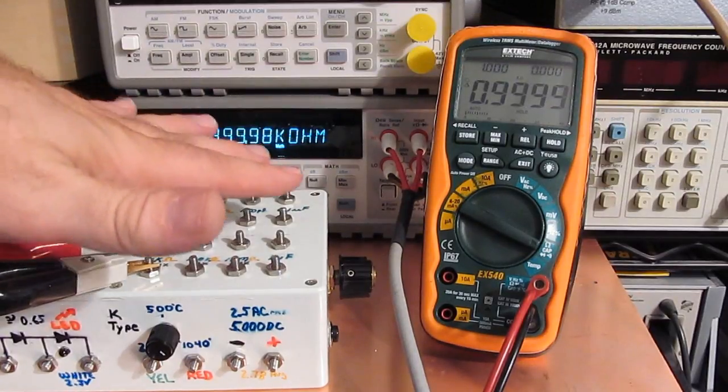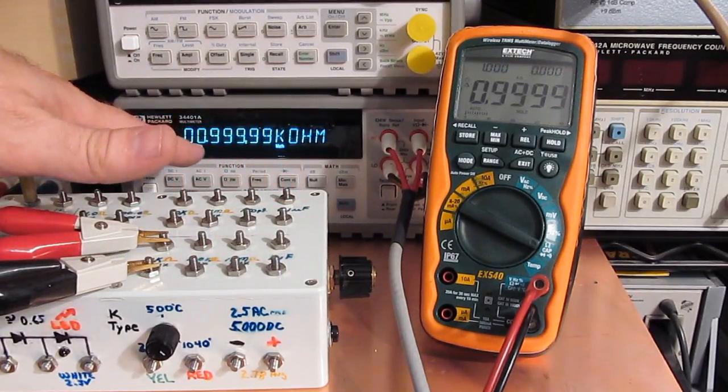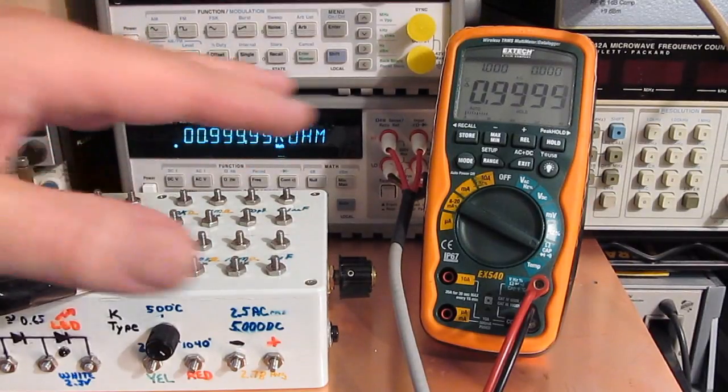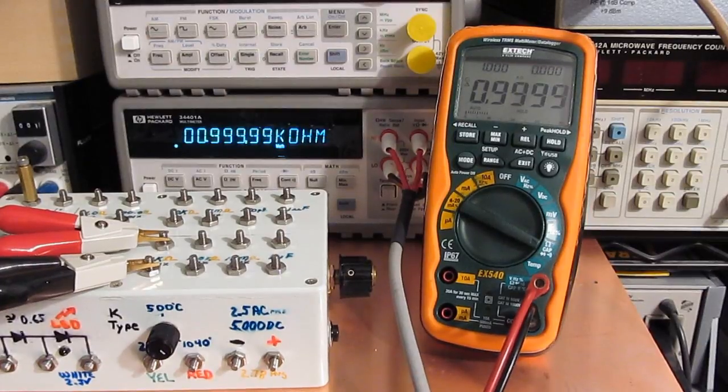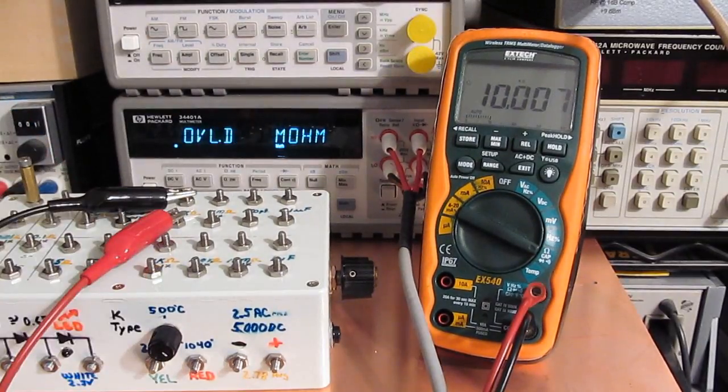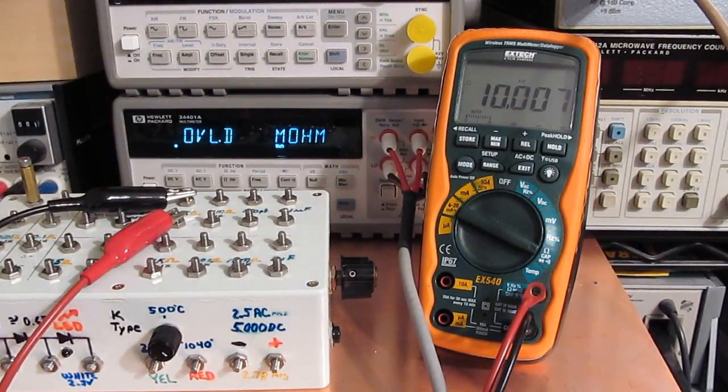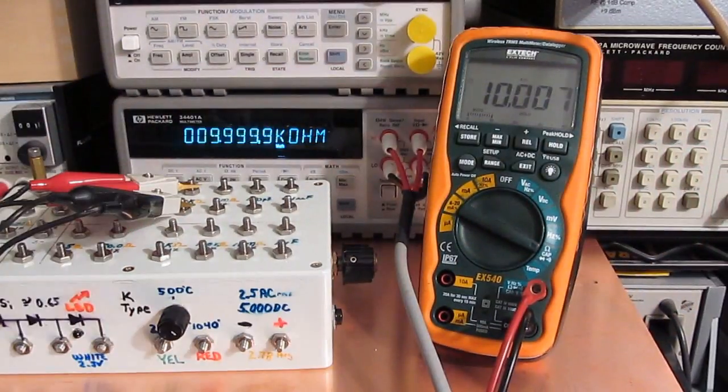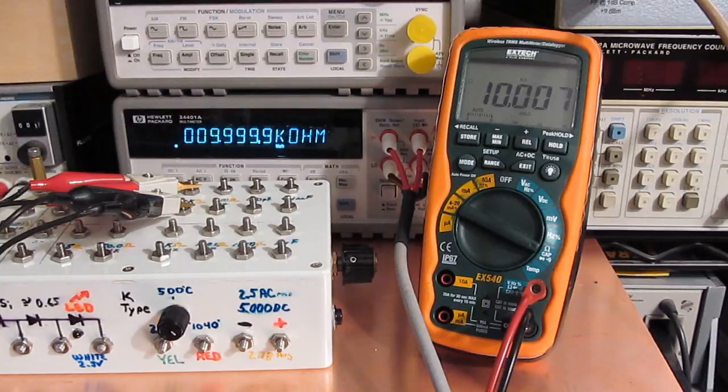I can see it moving around a little bit here as I kind of raised my hand over it. Again we are 0.99999k ohms. So again I'd say the Extech EX540 is pretty much dead on. With a 10k ohm resistor we are 9.9999k ohms with the HP and 10.007 with the Extech.